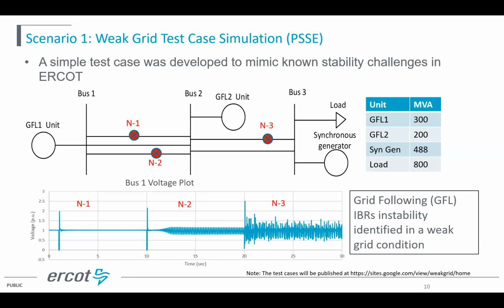So this is a simple test case that we created a few years ago to mimic the stability challenges in ERCOT. It's a simple 3-bus system. Bus 1 and bus 2 basically represent the remote area with high IBR penetration or concentration, and bus 3 basically represents the load center. We study an N-1-1-1 contingency. We first trip one line from bus 1 to bus 2 as N-1, then we trip another line from bus 1 to bus 2 as N-2, and then we trip another line from bus 2 to bus 3 as N-3. And as you can see, the PSCAD simulation indicates unstable or sustained oscillation, and the oscillation frequency is about 6 Hertz, a typical weak grid SSO phenomenon.